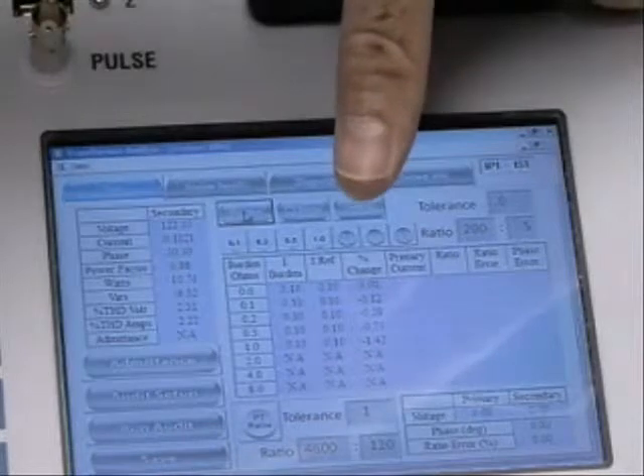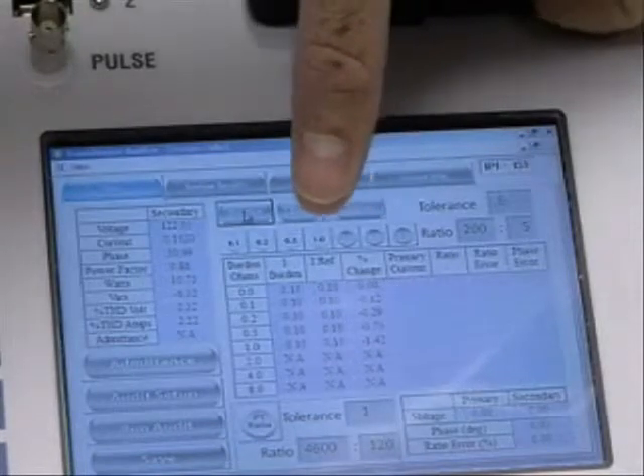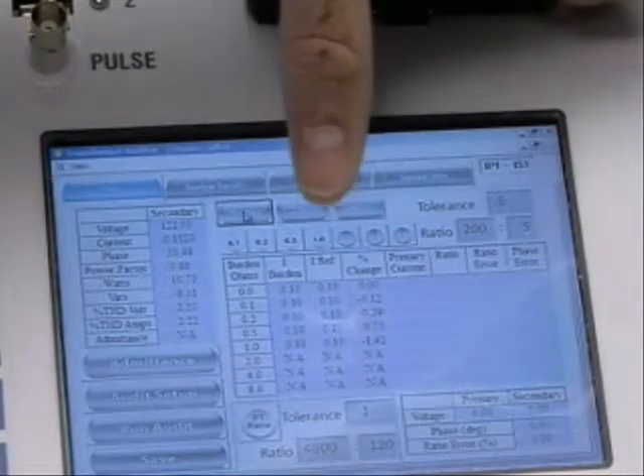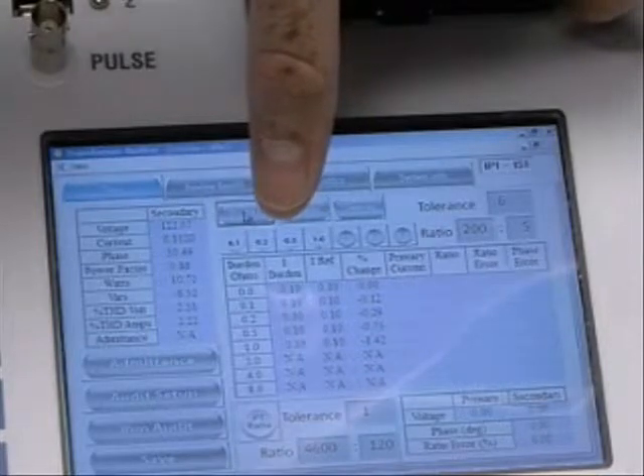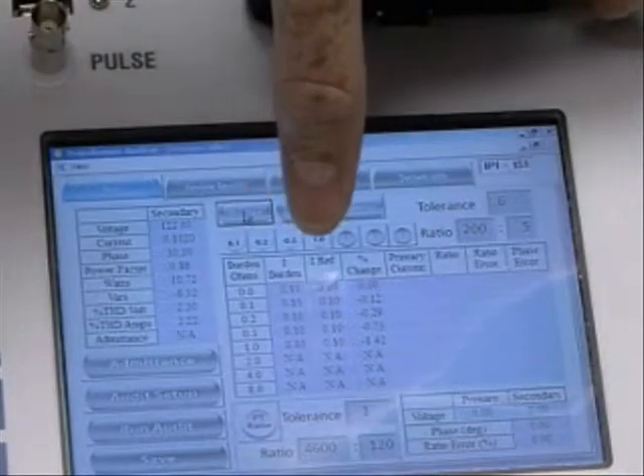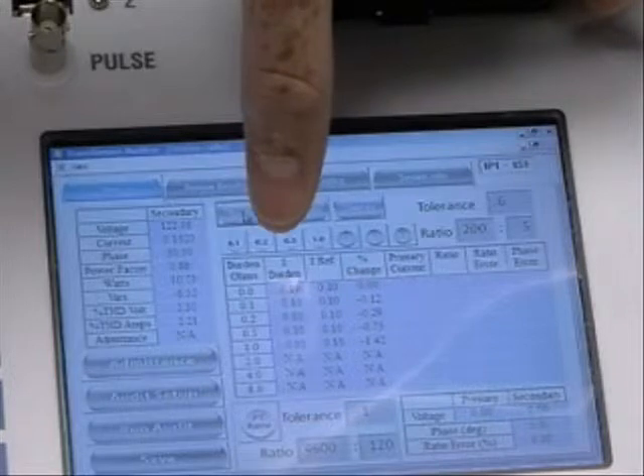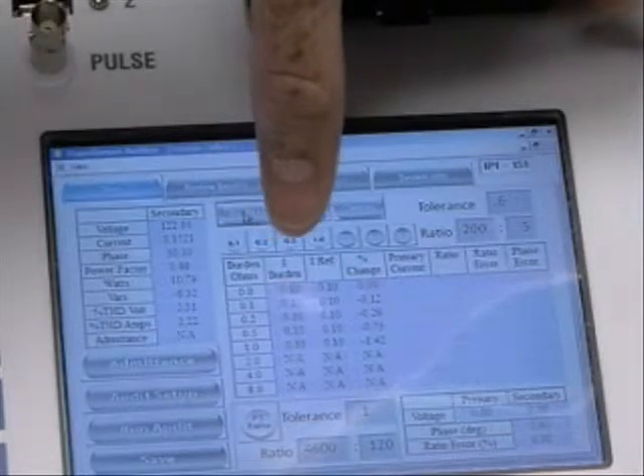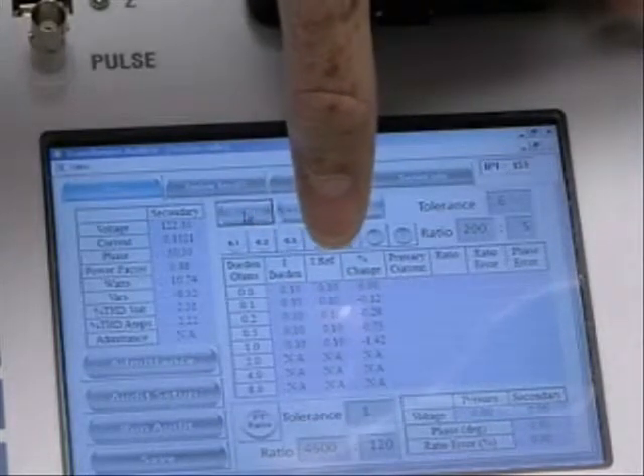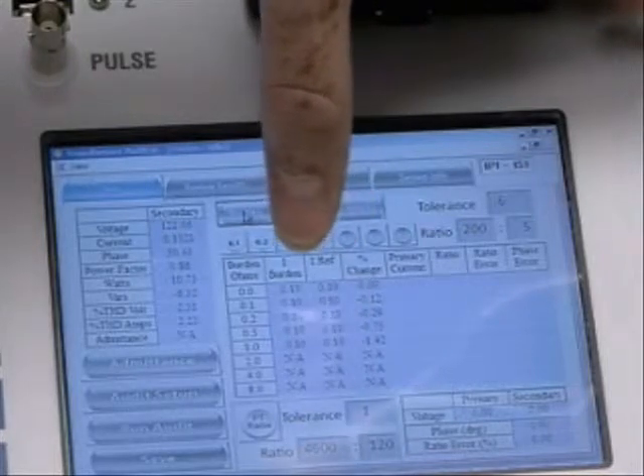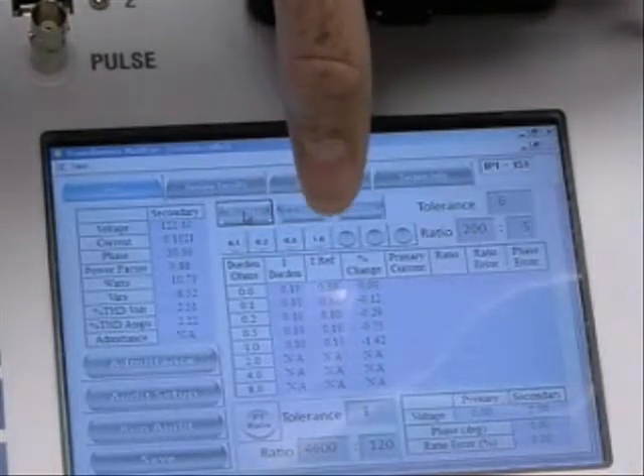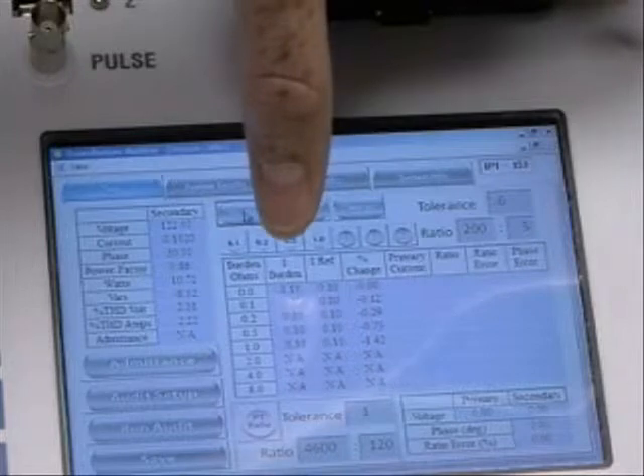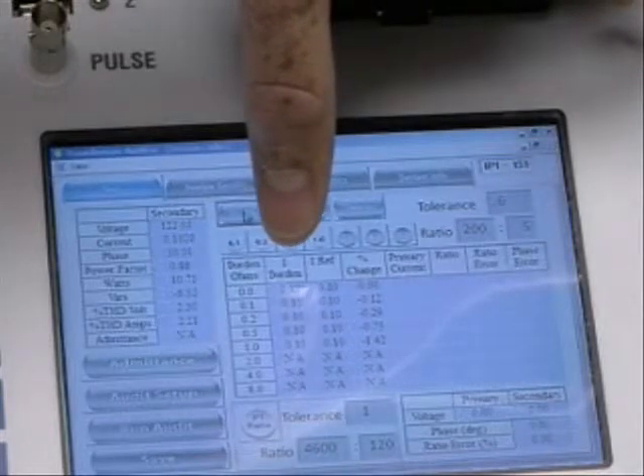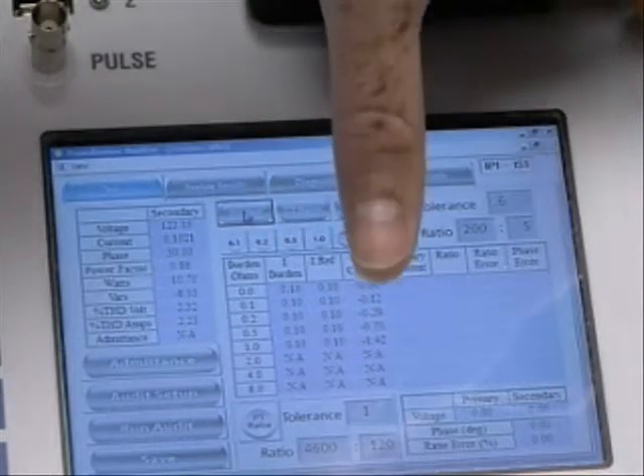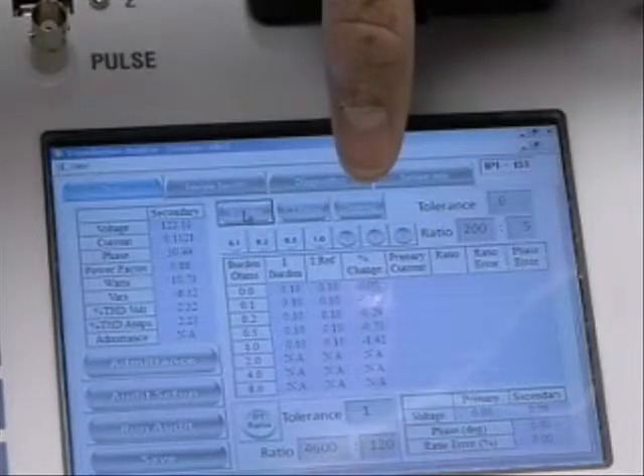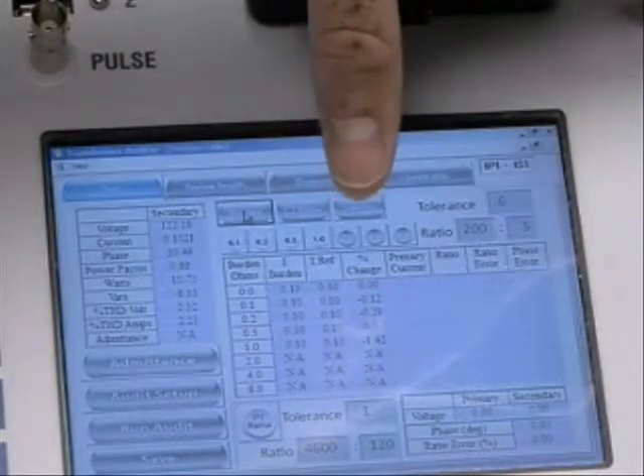But what you'll see is the percent change value change. What that percent change does is compare the amount of current without burden, that's the I reference, and the amount of current with burden, that's the I burden. Now we're only showing 2 decimals of resolution here, so you can't quite see the subtle difference between the reference and the actual current with the burden applied. But the percent change does show us the incremental change of those 2 comparisons.